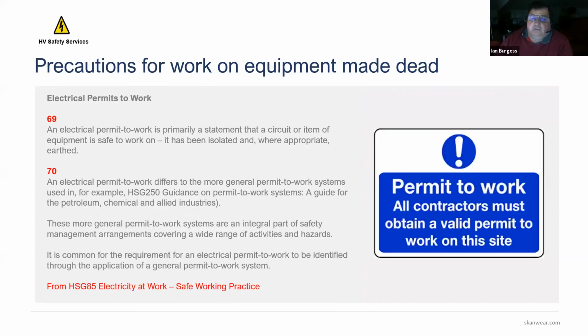This is from the guidance notes, and it suggests that an electrical permit to work is primarily a statement that a circuit or item of equipment has been made safe to work on, i.e. it's been isolated and, where appropriate, earthed. Now there's another document that covers permits to work, and that's HSG 250, a permit to work system. If you do a permit search within the UK, you will probably come across this document. It is not relevant for electrical working. It's a more general permit to work system, which came about following the Piper Alpha disaster many years ago. It's commonly used as a requirement for an electrical permit to be identified, but it is very clear within the guidance notes that that document shouldn't be applied within the electrical industry.